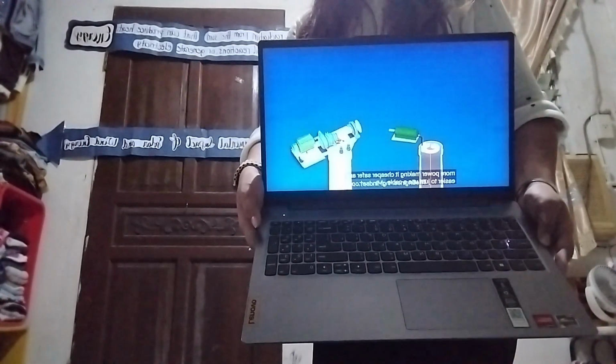Small turbines just use slip rings to avoid that, but large turbines produce a lot more power, making it cheaper, safer, and easier to just use a cable and track the rotations. Small wind turbines are typically direct drive. They often use permanent magnet generators like this one.